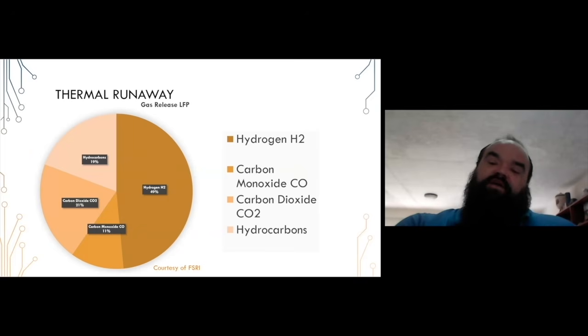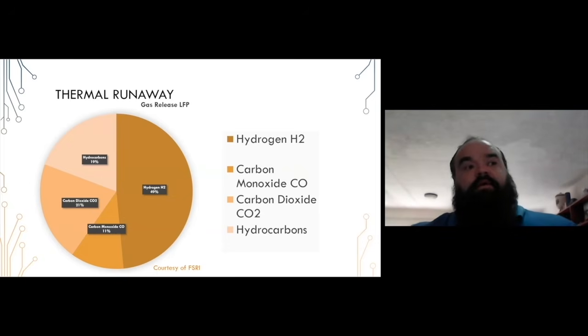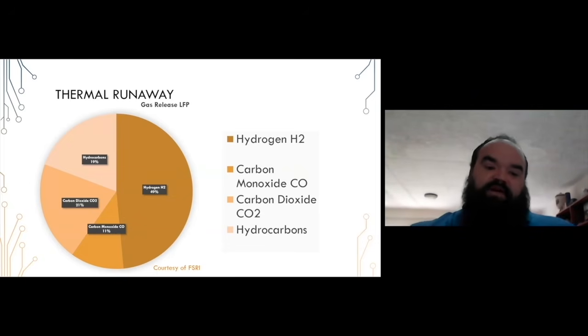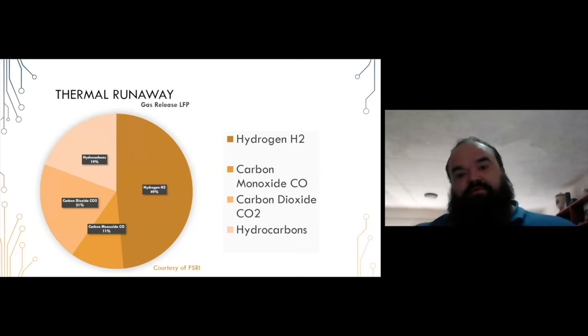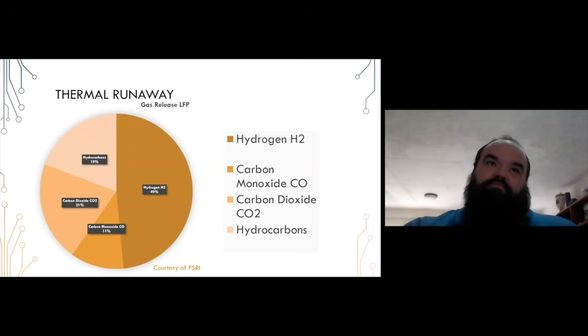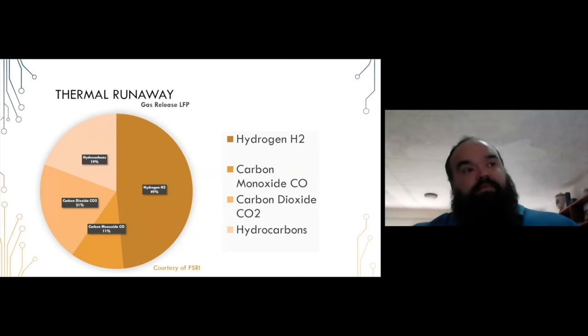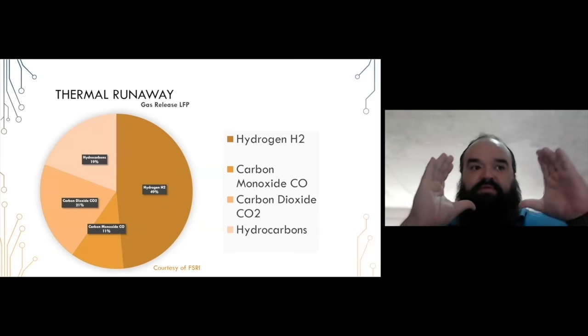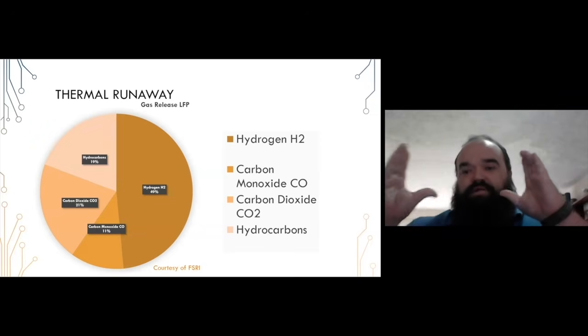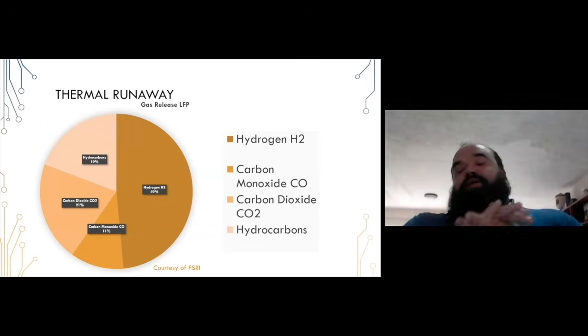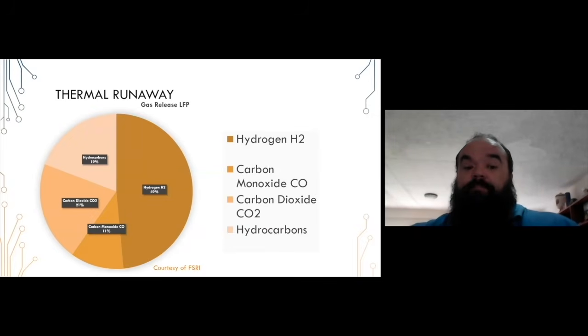This puts you in a very interesting sphere, because anyone who's worked in hazardous environments knows that hydrogen is extremely explosive. Hydrogen percentage in air from LEL to UEL is anywhere from 4 to about 70% volume, meaning if you've got a 3x3 room, you'd only need a 1 cubic meter portion of that 27 cubic meter room to have hydrogen in that volume of air for it to be explosive, which creates a big risk for secondary explosions.